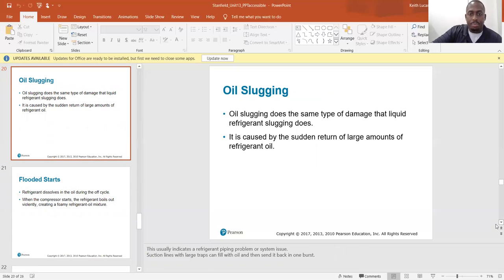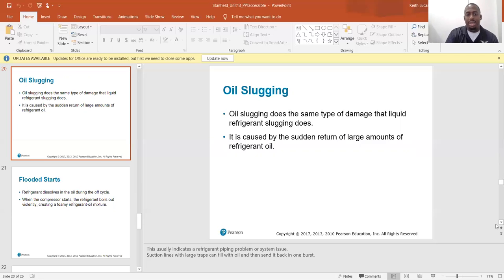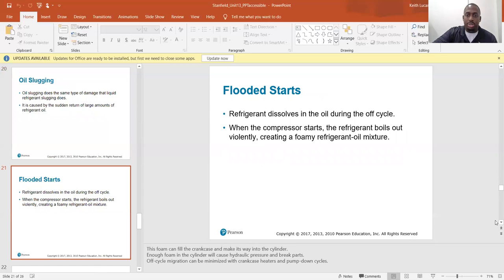Oil slugging does the same type of damage as liquid refrigerant slugging — it is caused by a sudden return of large amounts of refrigerant oil. This usually indicates a refrigerant piping problem or a system issue; suction lines with large traps can fill with oil and then send it back in one burst, overloading the compressor with oil all at once. This can break the valves and ruin the compressor, just like liquid refrigerant can.